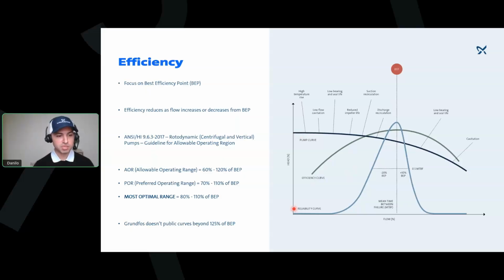When you want to make your selection, at the bottom you have the flow and head, which is the pressure you need to overcome. Once you find that point, you identify on the pump curve the duty condition of your pump. One thing to keep in mind is that when you're sizing and selecting a pump, you always have to look at the best efficiency point, the BEP. You have to look at the efficiency curve. As a rule of thumb, a lot of people, and I understand, I've been in that place before, if you don't have much knowledge yet about pumps, once you find your duty condition you just want to be right in the middle of the curve, correct? Wrong. If you don't analyze the efficiency curve, you cannot tell.